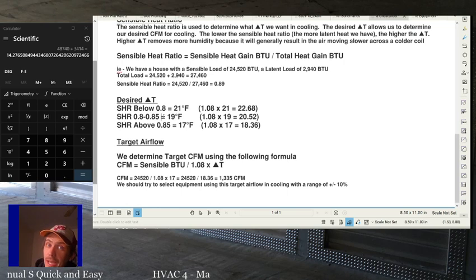That's not always the case, though. It's not always the case that a 20 degree delta T or so is correct. But in the majority of cases, it's a pretty safe bet. But that's not how we figure out what it should be. All right. And then finally, an SHR above 0.85, which is a pretty low latent load, right, is a 17 degree delta T, which is what we had up here. We had a 0.89 sensible heat ratio, so that means we would want a 17 degree delta on this equipment. That's uncommon, right? But it's possible that's what you want.